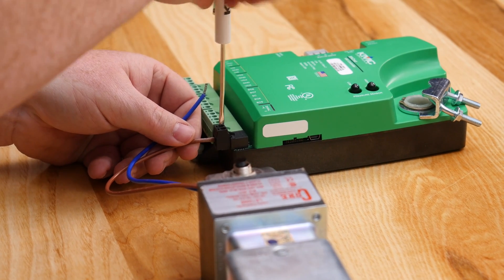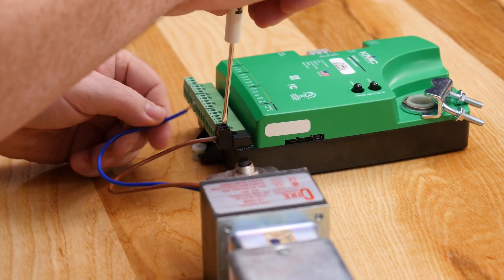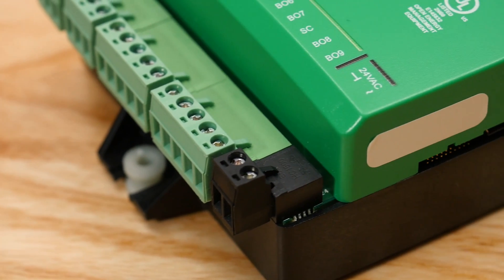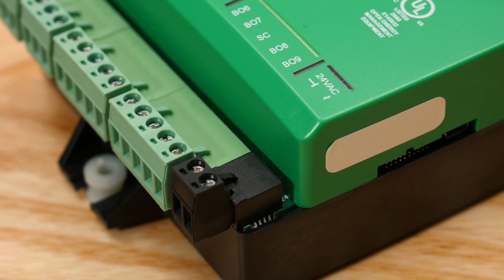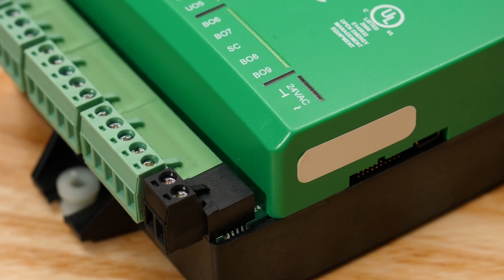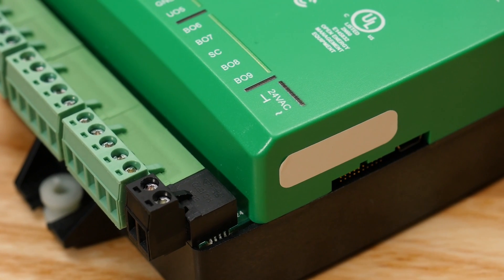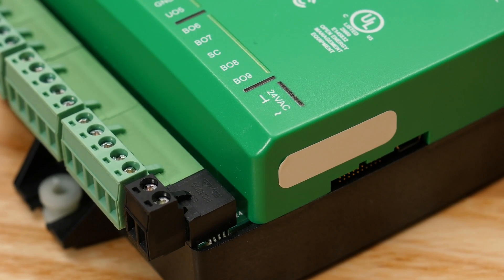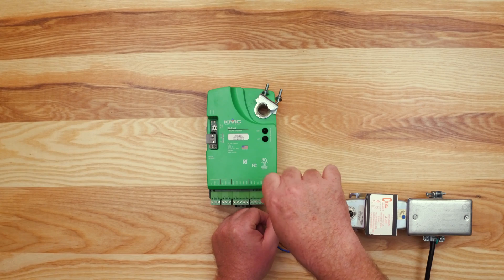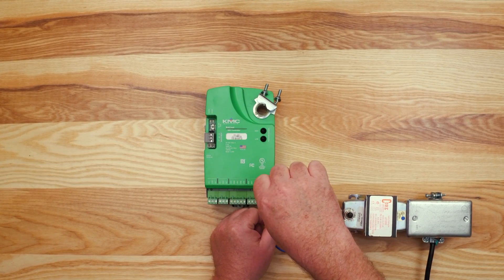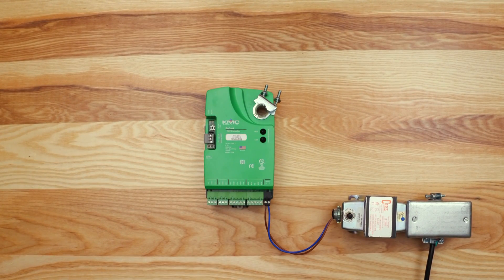When wiring, note the polarity of the controller's terminals. The common terminal is represented by a T shape and the phase terminal is shown as a wavy line. This is very important. If wired incorrectly, the controller could be damaged and need replaced.